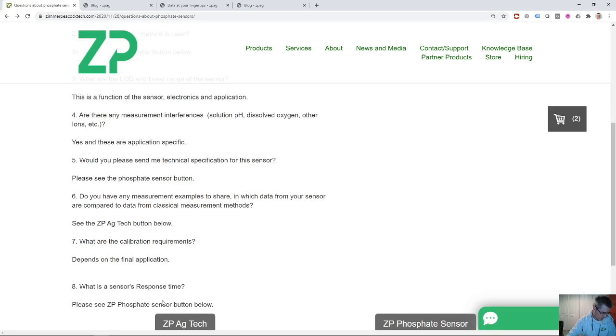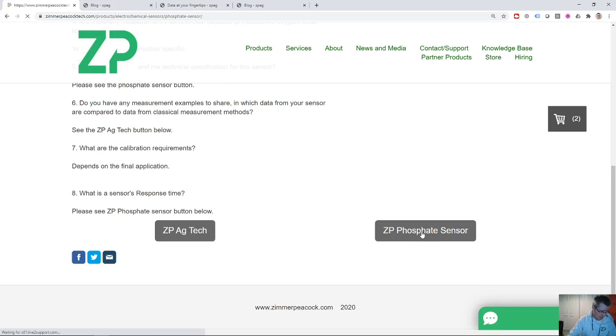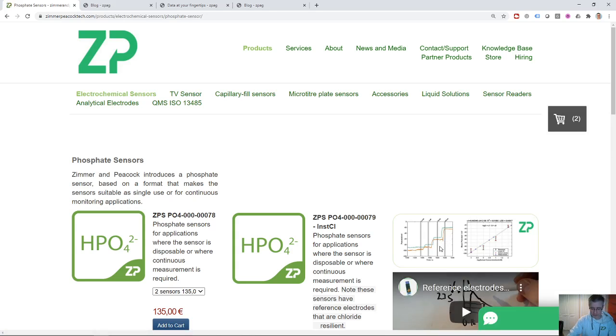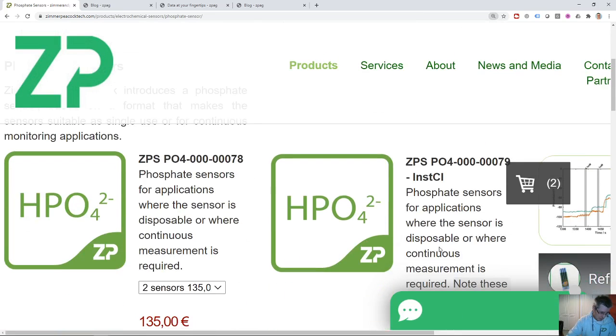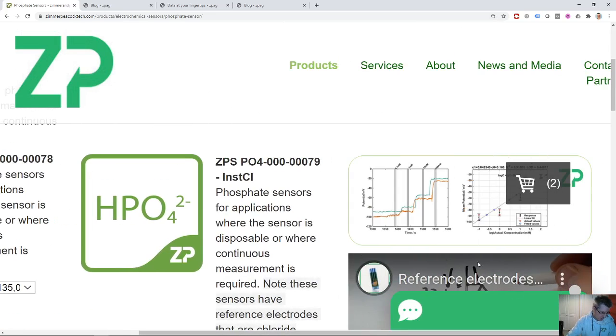And then the question here is, what is the sensor's response time? Again, it's in the raw data. If you come and look at this page, I can see here that this sensor is reaching its T90, 90% of its signal, in really just some single seconds. I can see here that that's 50 seconds along here, so it takes a fraction of that to actually reach its plateau. So it's responding quite quickly.